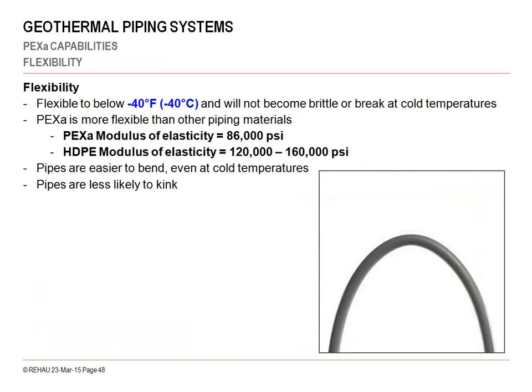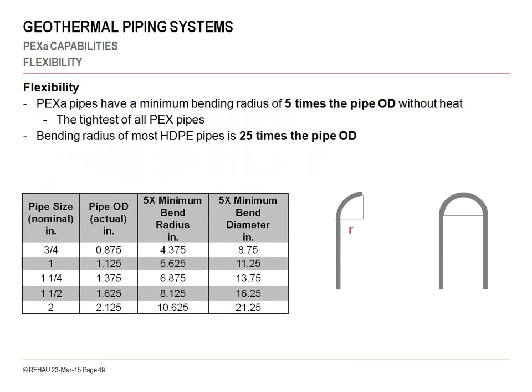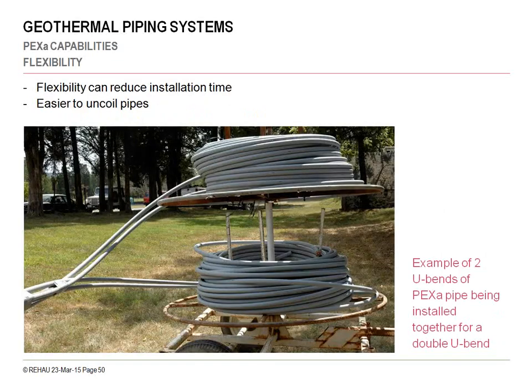Flexibility of PEX-A pipes. You can see the modulus of elasticity at 86,000 psi compared to the HDPE material. HDPE gets down to a bend radius of about 25 times the OD of the pipe. Because of the cross-linking of the PEX-A material, we can get it down to about 5 times the OD without kinking of the pipe. So here we're showing you on different pipe sizes the radius and diameter with the PEX-A pipe. As I mentioned, it's 5 times the OD of the piping material. Again, here are 2 coils of PEX-A pipe, just showing the flexibility and ease of uncoiling the pipe material.